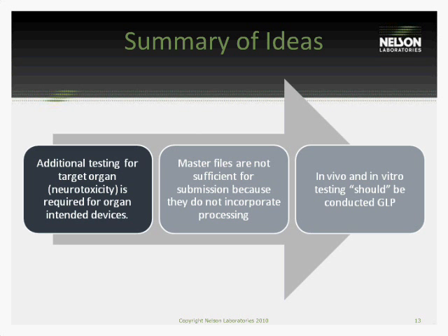The next topic is in vivo and in vitro testing should be conducted GLP. Now, I'm not going to spend a lot of time on that because if you're really spending this much time and money on biocompatibility, the small increase in GLP costs should be worth it. For those of you who are not sure what GLP means, it stands for Good Laboratory Practices. It's kind of a quality built into that test. The testing is performed exactly the same, but it's audited by an independent quality group. And so the FDA prefers to see the GLP tests performed for biocompatibility.